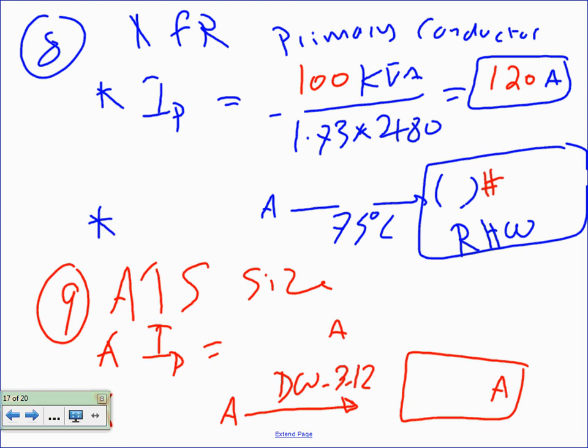Now do me a favor here. I need somebody to do the math because I didn't do the math. I did it differently from time to time, guys. Sometimes I multiply by 1.25. This is really opinion because it's continuous load. Sometimes I don't. But get into the habit, being an engineer, we don't pay for the copper anyway, right? So we dump that copper there.